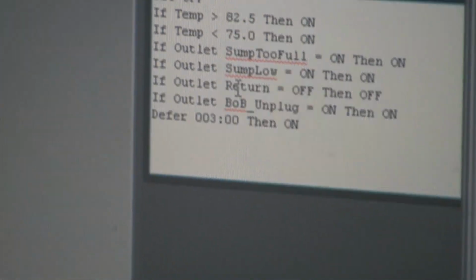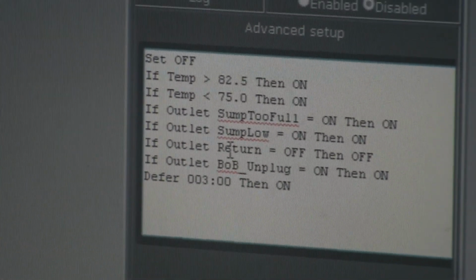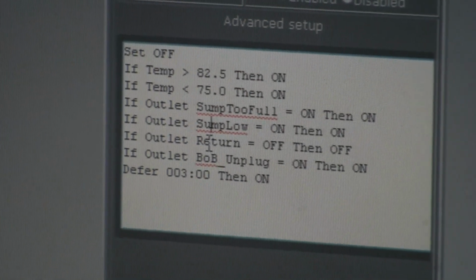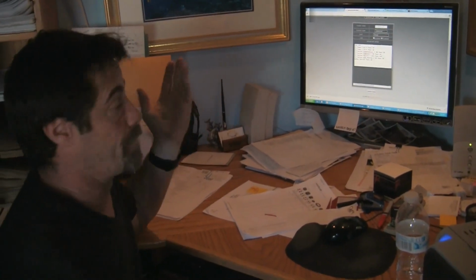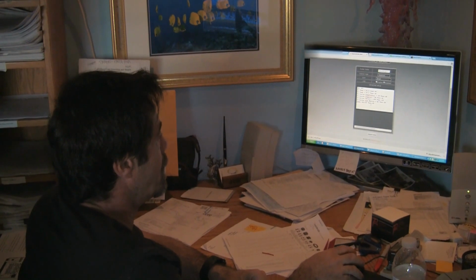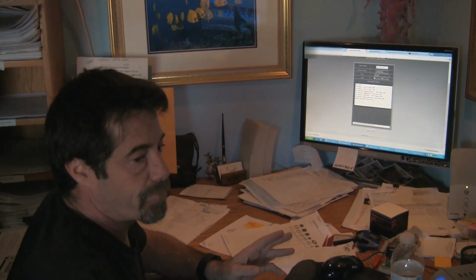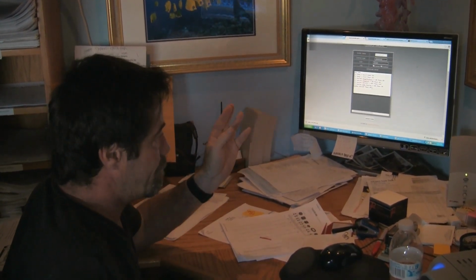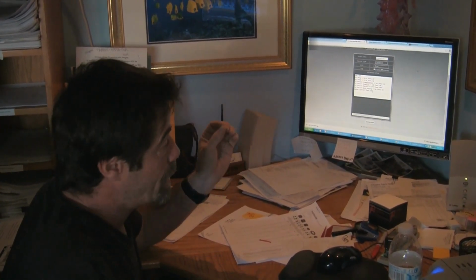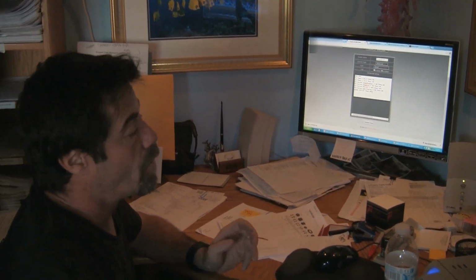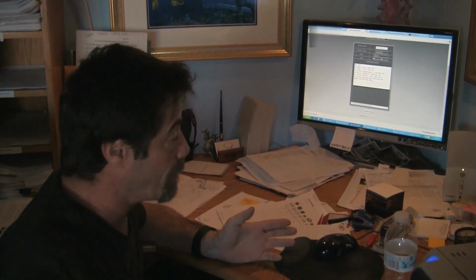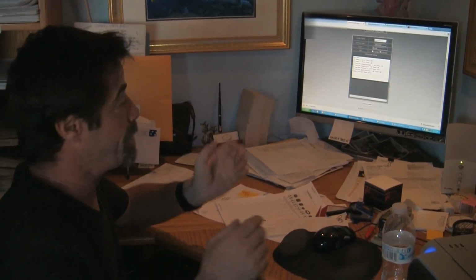If his return pump is shut off, he's not going to get an email alarm, because that might cause his sump to be too full. So if he's doing maintenance and shuts his return pump off, he doesn't need to be alerted that his sump is too full. If his breakout box is unplugged, he'll get an email alarm. Any of these alarms will be deferred for 3 minutes, meaning the state of sump too full or too low needs to persist for 3 minutes. That way, if he's working on the sump and bumps a float switch, he won't get an inadvertent alarm immediately -- it has to stay in that state for 3 minutes.